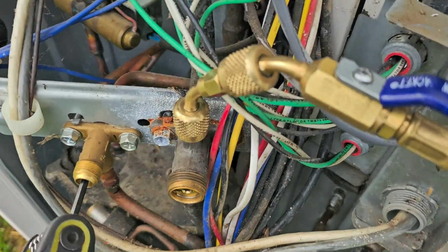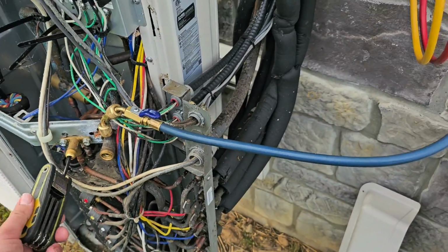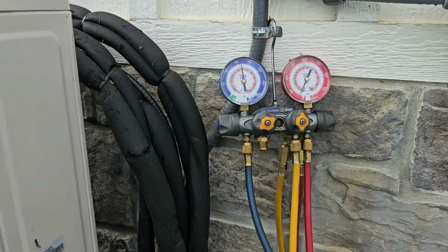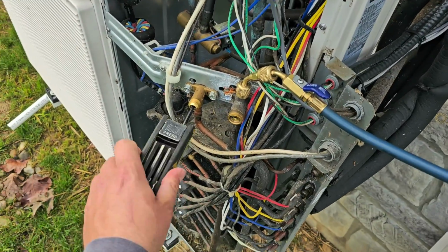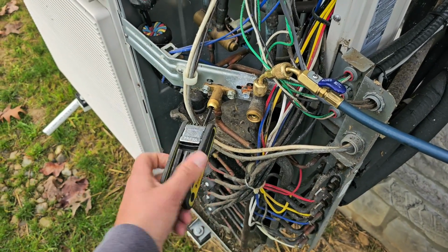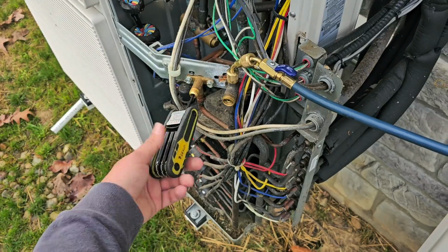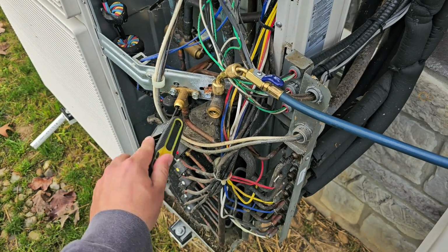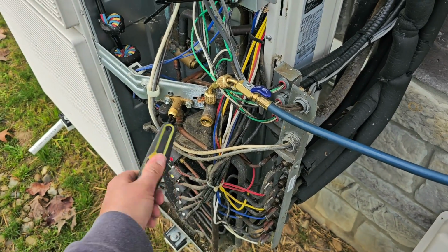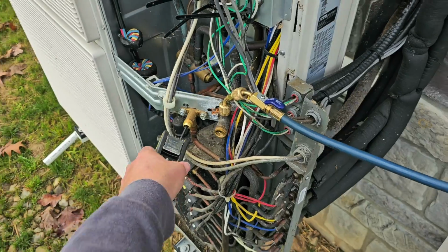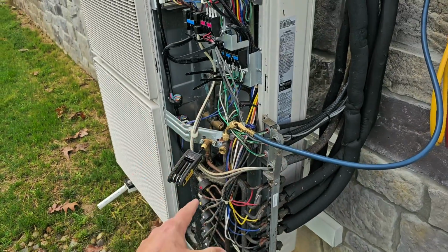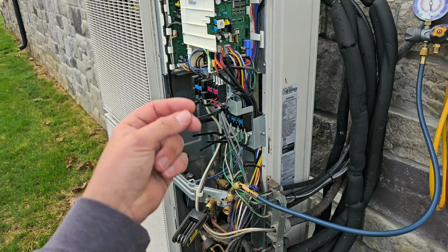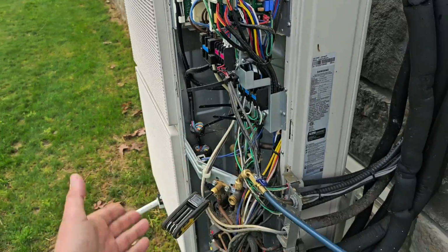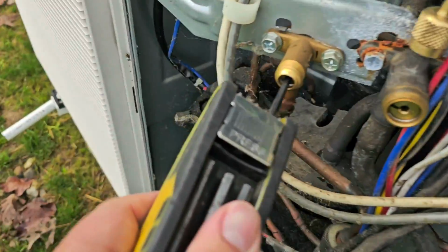I've got the 1/4 inch to 5/16 adapter. That way I can hook up the hose and the gauges. That way I can know when to close the suction line service valve. And we've got to pump all that refrigerant from all those indoor units, all those indoor heads, into the outdoor unit before we can disconnect those copper connections or flare connections to that ducted unit, so we can actually remove it. So I've got the liquid line service valve closed. I'm ready for the pump down.